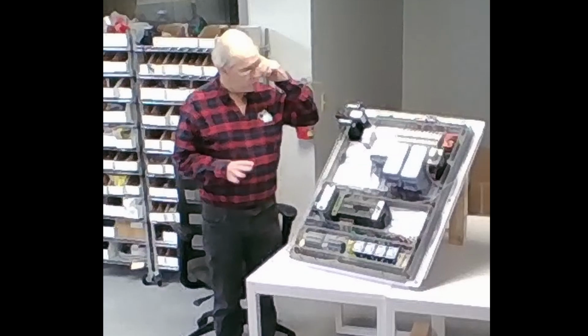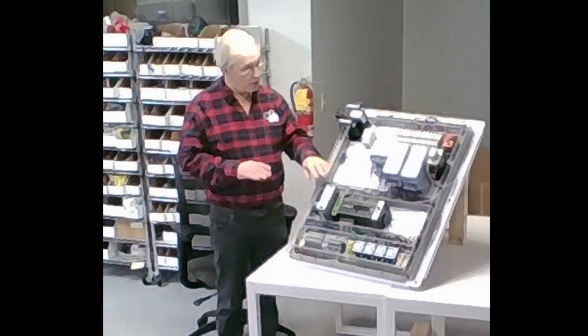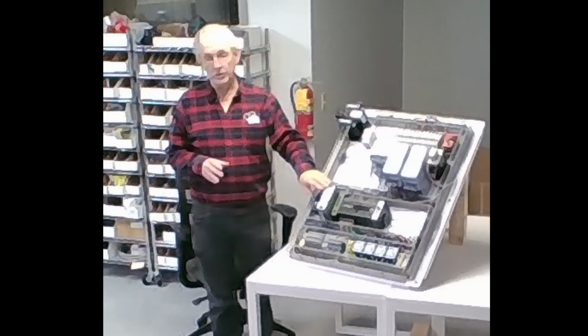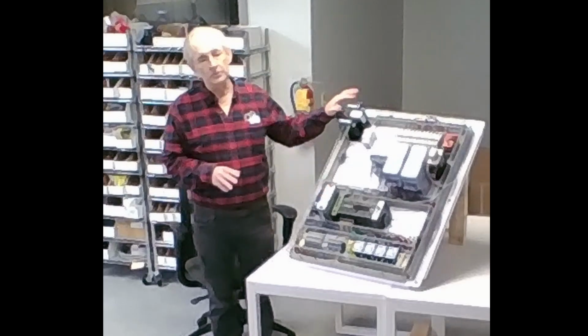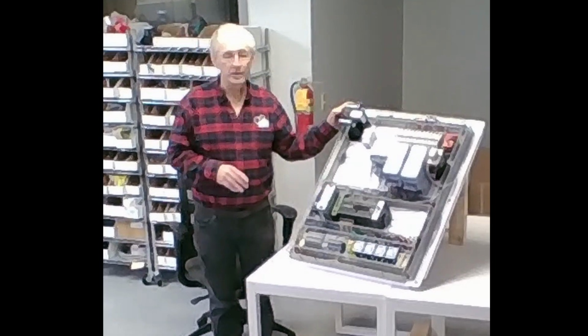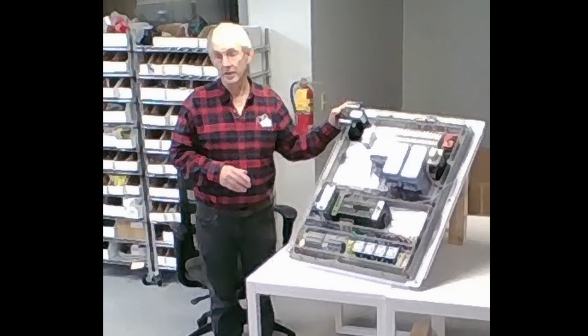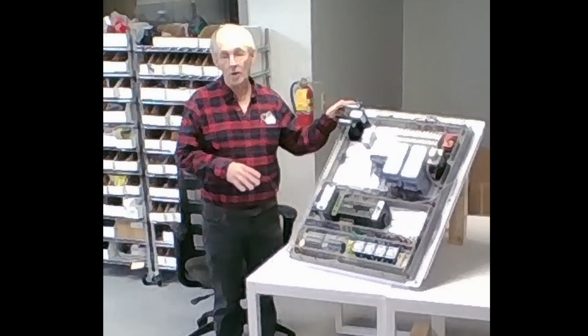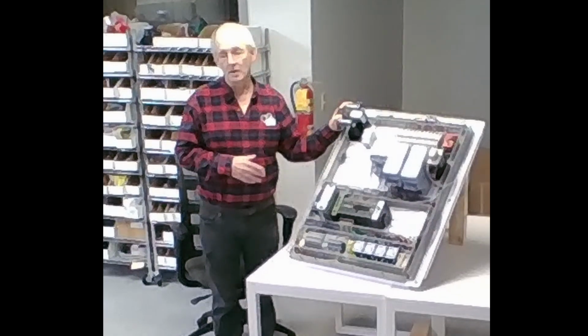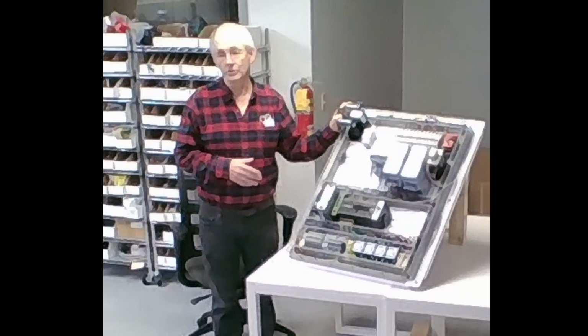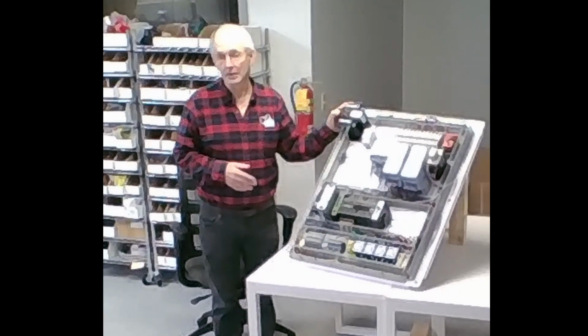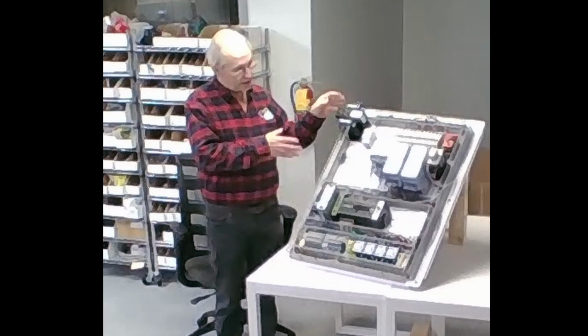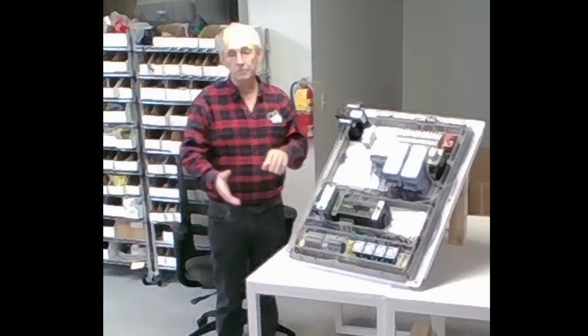So the 120 volt AC is our AC control voltage, and we're using a transformer to do this. We could bring the 240 directly to other things that have a wide-ranging input, but the reason for using a transformer is to get some protection against lightning and surges and such, because the magnetic coupling in here won't pass an enormous surge of current. It'll just get soaked up in the transformer. So we try to build things with multiple levels of protection.